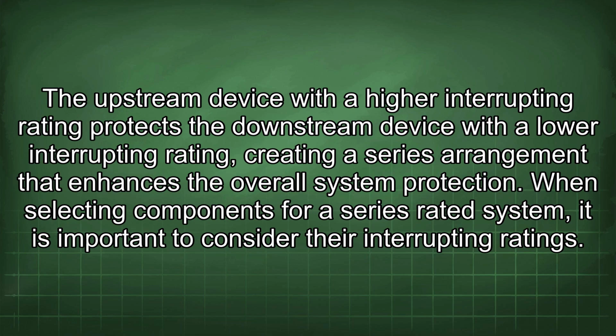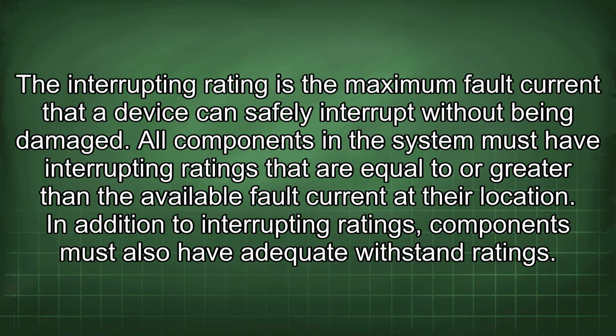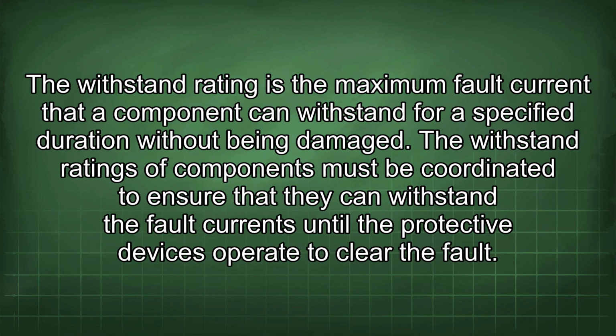When selecting components for a series-rated system, it is important to consider their interrupting ratings. The interrupting rating is the maximum fault current that a device can safely interrupt without being damaged. All components in the system must have interrupting ratings that are equal to or greater than the available fault current at their location. In addition to interrupting ratings, components must also have adequate withstand ratings. The withstand rating is the maximum fault current that a component can withstand for a specified duration without being damaged. The withstand ratings of components must be coordinated to ensure that they can withstand the fault currents until the protective devices operate to clear the fault.